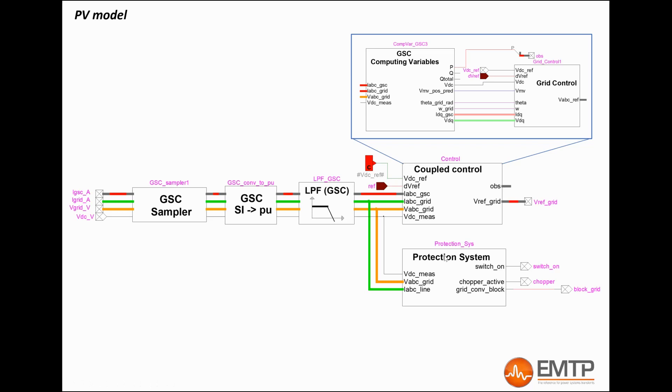The EMTP 4.1 generic model is controlled using vector control techniques in the DQ0 domain. This control type is very commonly used by PV converter manufacturers. Some of its big advantages is that it allows decoupled control of real and reactive powers. The real power is only controlled by the D-axis and the reactive power is only controlled by the Q-axis.